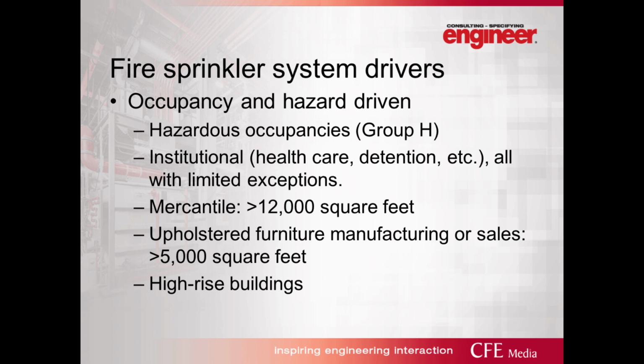Now, mercantile occupancies, retail, those types of occupancies are typically required to be sprinkled if you're over 12,000 square feet. And again, there is a special requirement for occupancies that contain upholstered furniture manufacturing or sales. That's considered to be a higher hazard. There's a lot of foam plastic in the construction and production of upholstered furniture. And when those occupancies are in excess of 5,000 square feet, they'd be required to be sprinkled. Now, high-rise buildings are also required to be sprinkled. That's been a requirement in the code since the mid-'80s. There used to be a compartmentation option, so you will still find existing high-rise buildings that are not sprinkled, but those were built prior to the requirement.